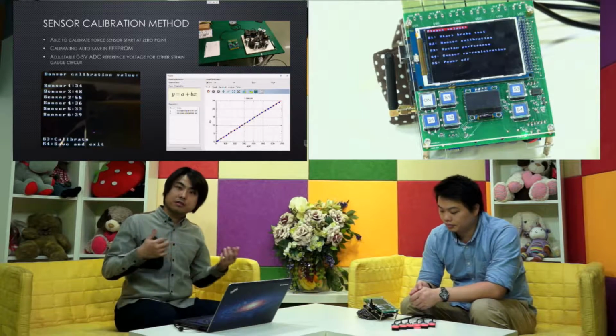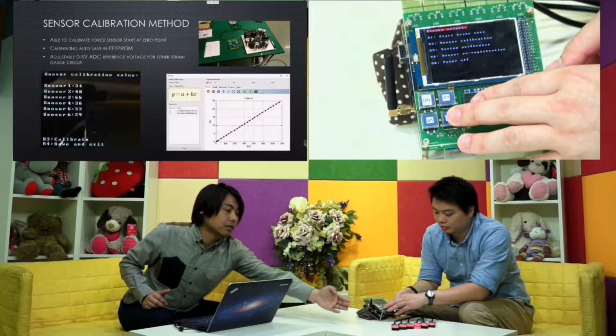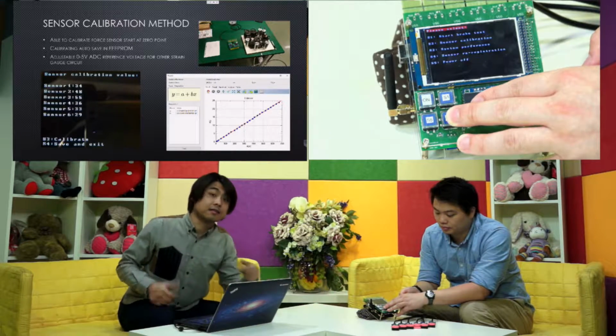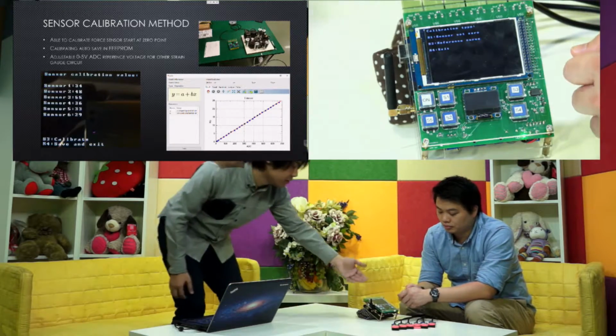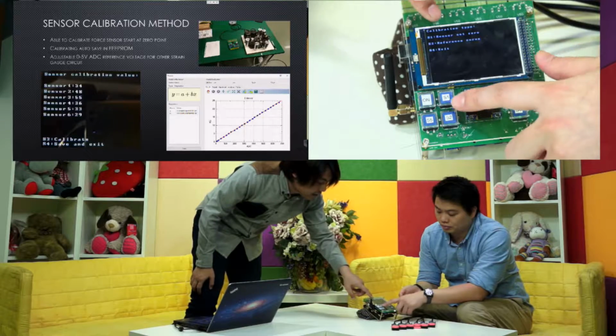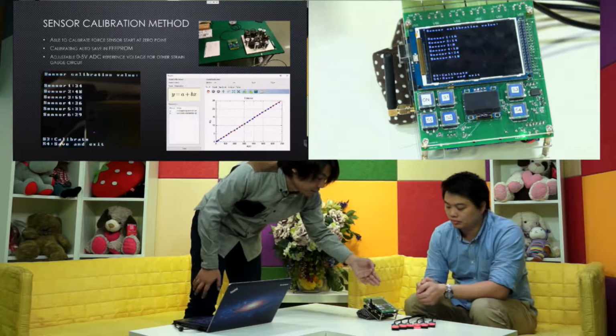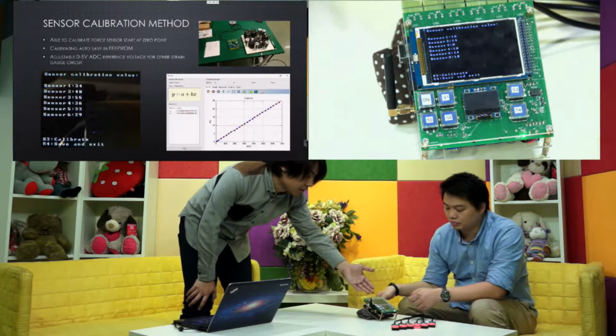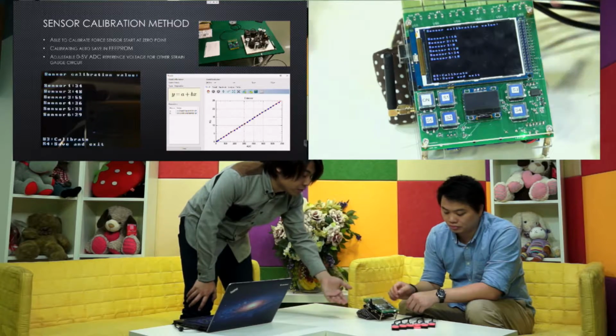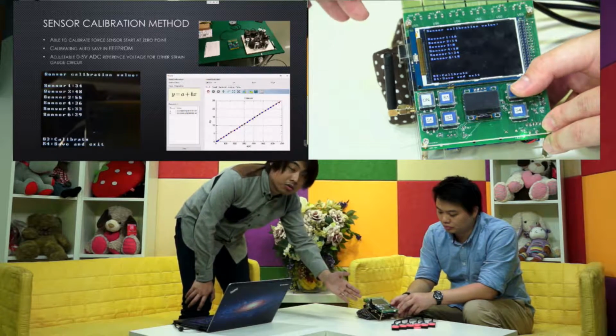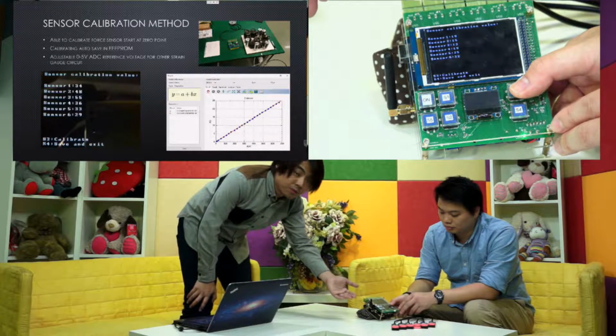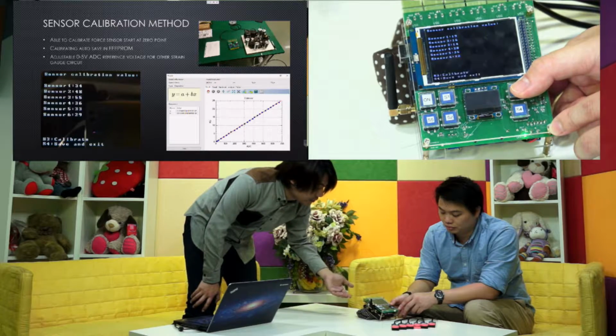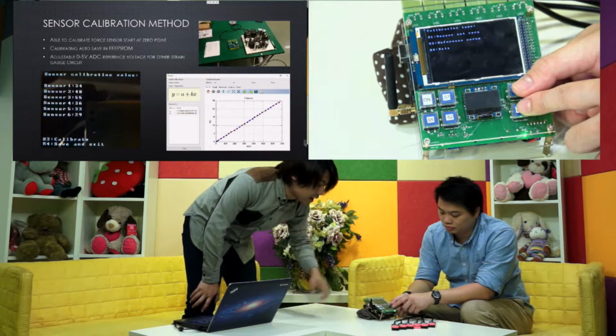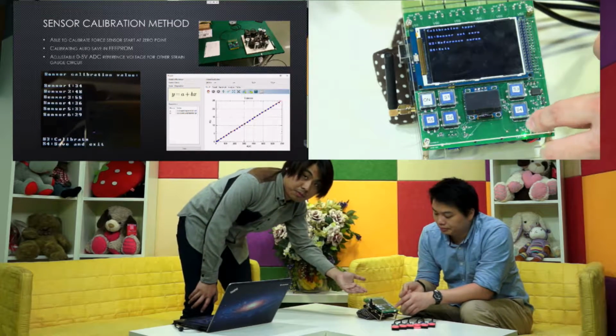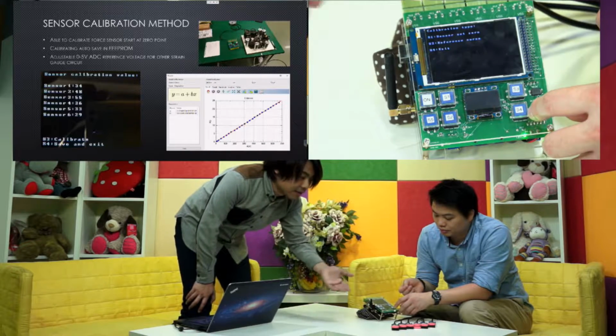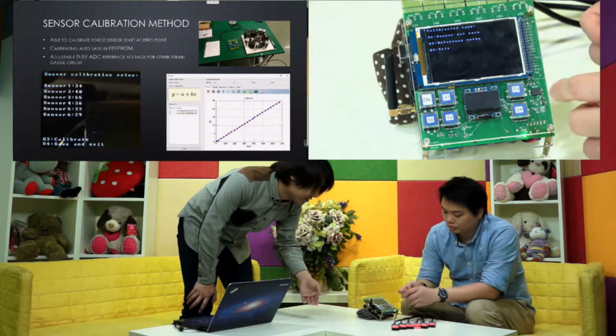Okay, the method is so easy. When you don't apply any force to the sensor, that is 0. So we have a mechanism to take this 0 point. Just go to sensor calibration and sensor set 0. Just press enter. This level was calibrated last time. Why does the device show this? Because all the data is stored in the EEPROM. Now we calibrate again, then save and exit. Now all the calibrated data is saved to the EEPROM. Even if you close the device, the sensor does not need to be recalibrated again.